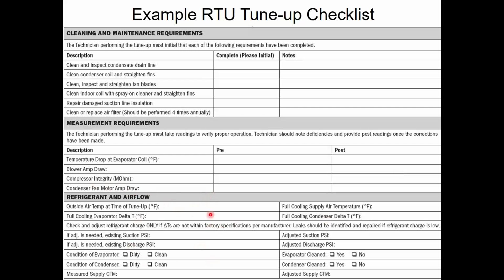And then down at the bottom we have some airflow and refrigerant things. The refrigerant things are easy for HVAC techs to measure. The airflow: measured supply CFM and adjusted supply CFM. CFM is cubic feet per minute of the air volume. Believe it or not, HVAC techs typically do not have tools to measure airflow.